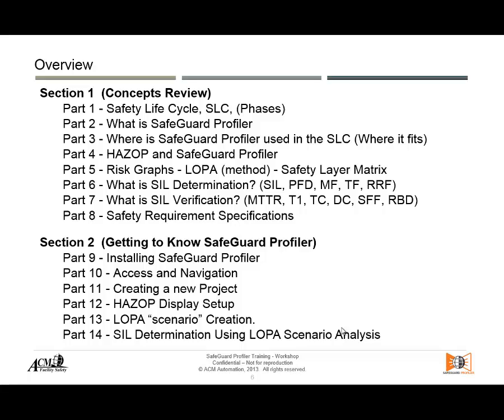The second part of this first section covers SIL verification: mean time to restore, proof testing, test coverage, diagnostic coverage, safety failure fraction, reliability block diagrams, and safety requirements specifications. When I present the safety life cycle, you will see where safety requirements specifications fit and why they are important — and why they are included in the Safeguard Profiler tool.